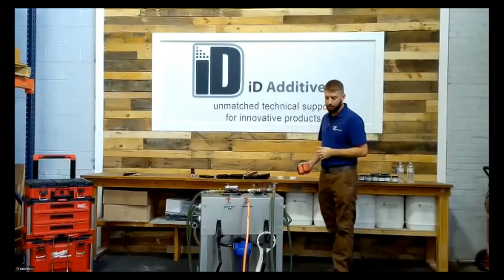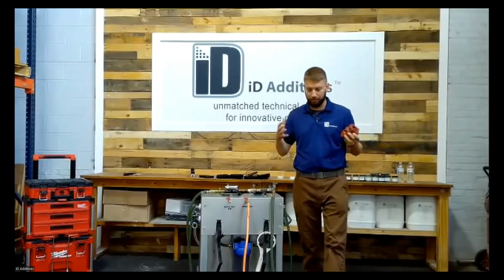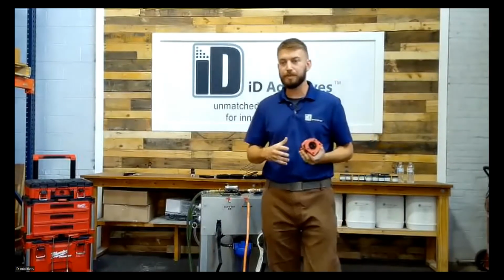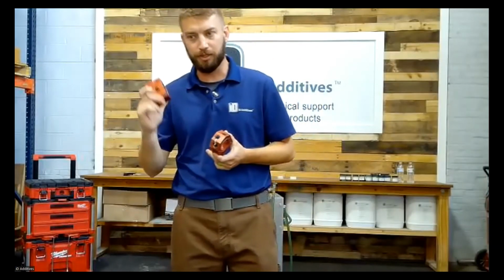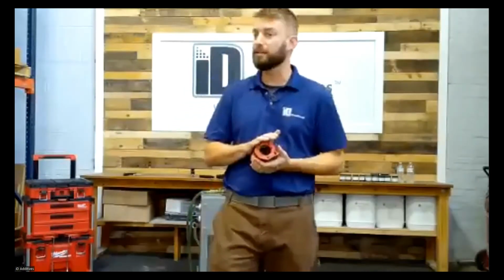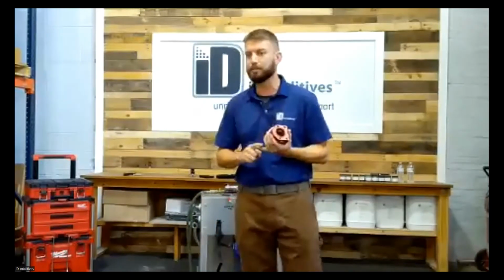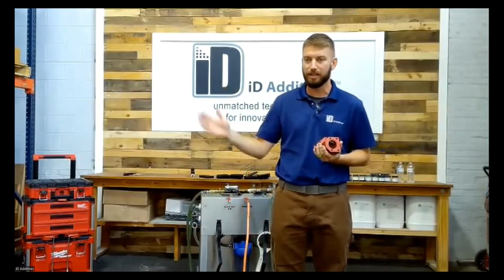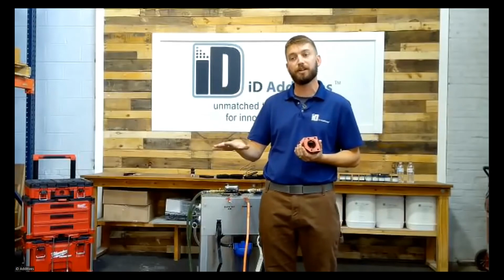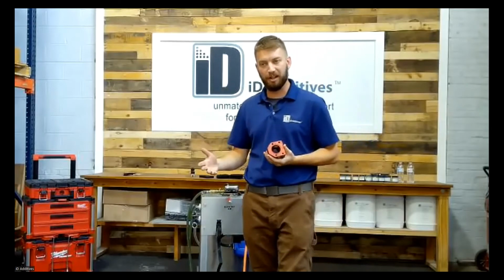Okay, well, your manifolds are the first spot that water hits. Now these are off of mod blocks, not tubular, they're anodized aluminum. The EcoPro 360 will not etch any metals, whether they are ferrous or non-ferrous. They will, if left exposed, tint your non-ferrous metals. Typically I run into beryllium, copper, and aluminum, but that's, again, if you don't wipe it dry and it's left to sit on there, you'd have to go back and do some polishing work.